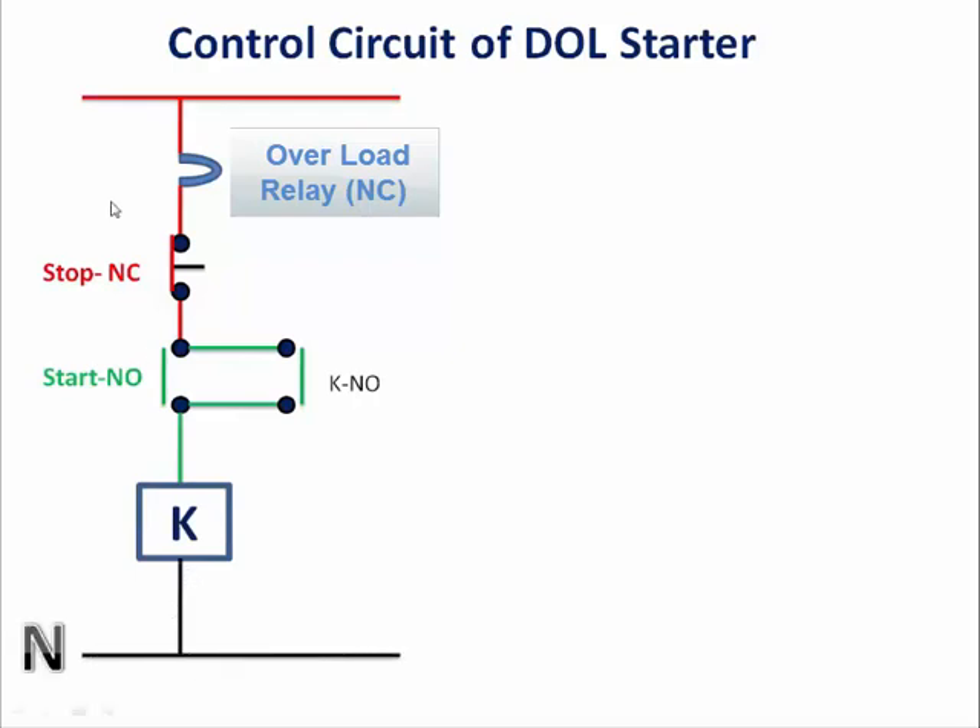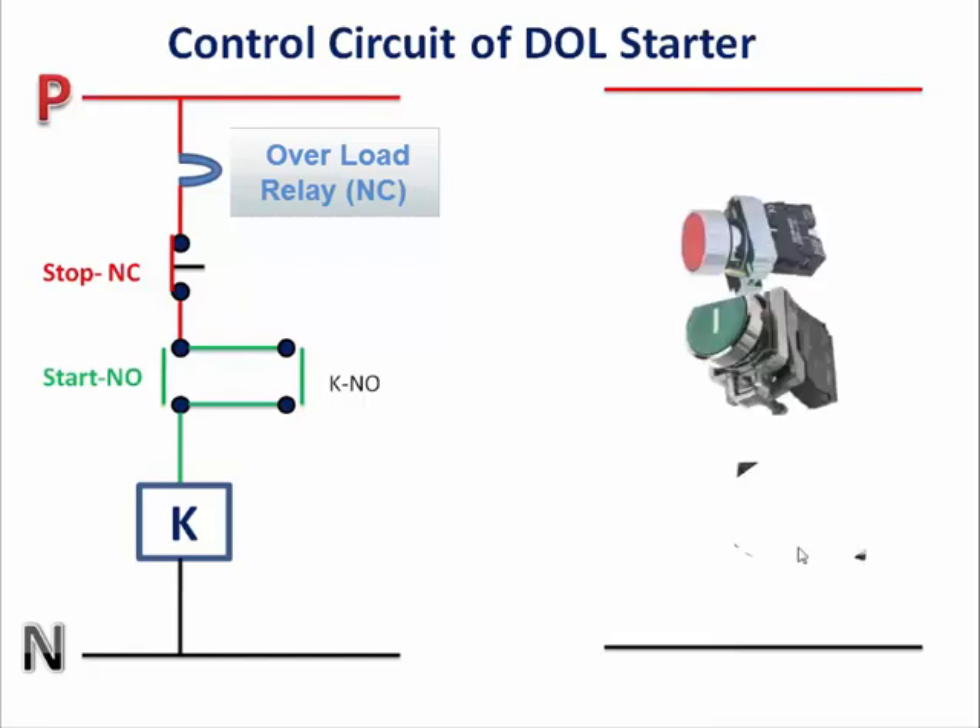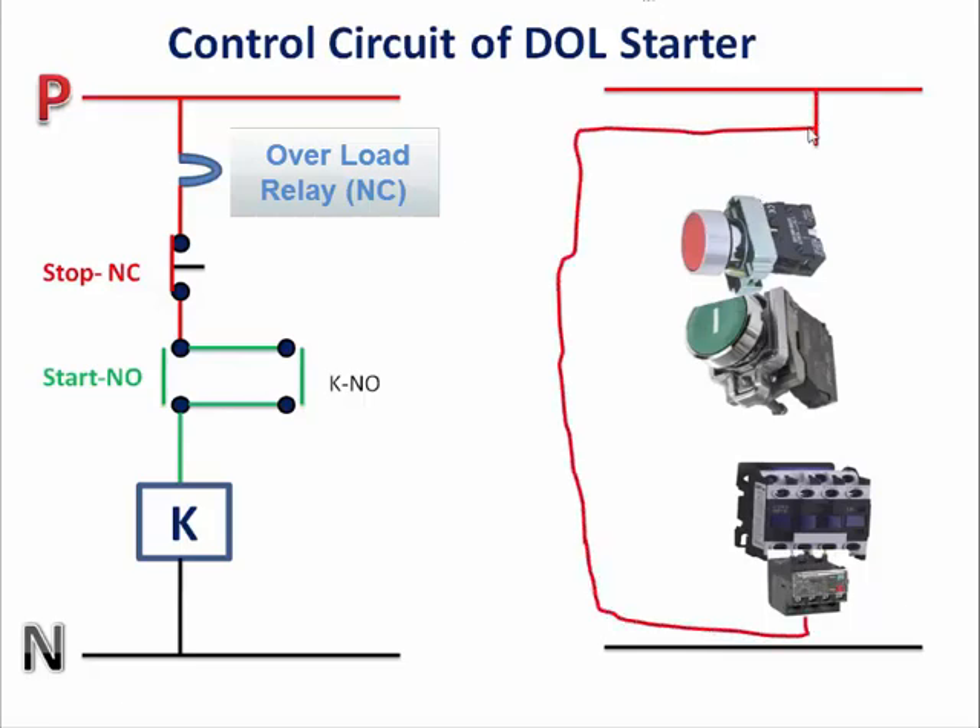The left hand side shows the electrical control circuit for DOL starter and the right hand side shows the component-wise connection. We will take the phase first and connect it to the overload NC contact, then connect it through the NC contact of the stop push button. You can match right hand side and left hand side in a similar manner.